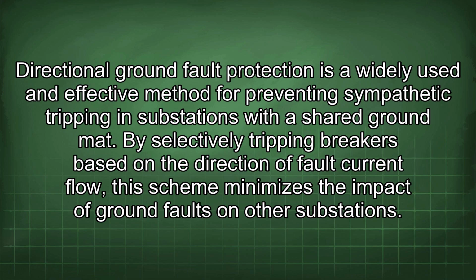Directional ground fault protection is a widely used and effective method for preventing sympathetic tripping in substations with a shared ground mat. By selectively tripping breakers based on the direction of fault current flow, this scheme minimizes the impact of ground faults on other substations.